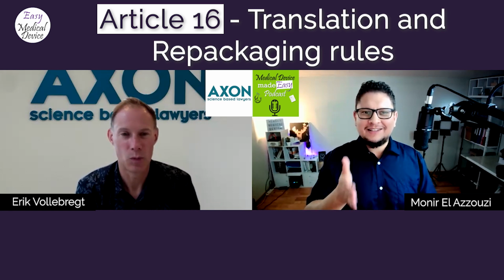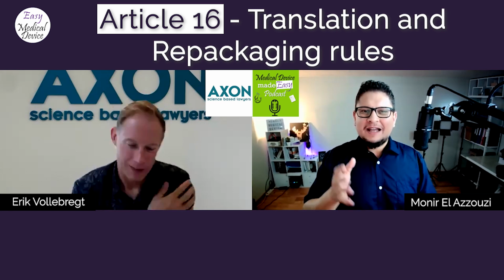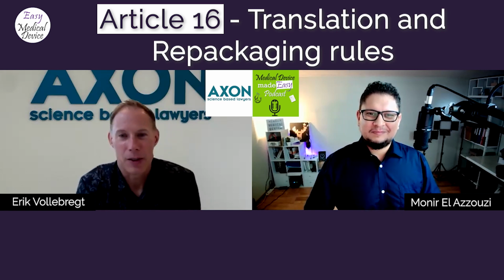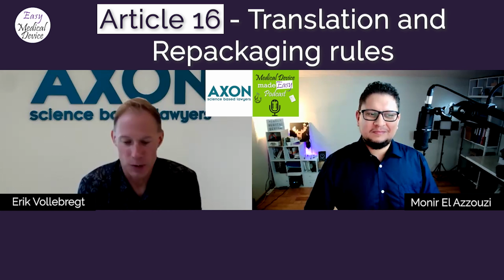So what is that line exactly? When can we say, I am in it or I am out of it? Right. Yeah, so Article 16 concerns devices that have been placed on the market. Article 16(1)(c), which is the starting provision for the rest of the article as we're going to discuss it, says that you become a manufacturer if you modify a device already placed on the market in such a way that compliance with the applicable requirements may be affected.